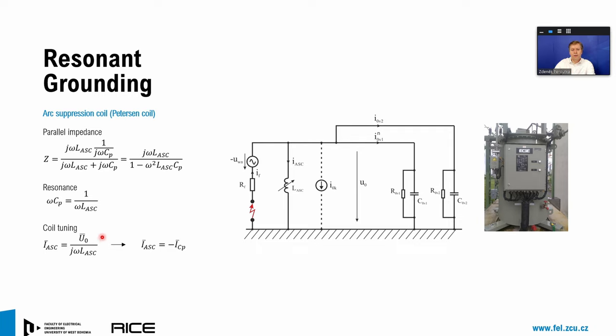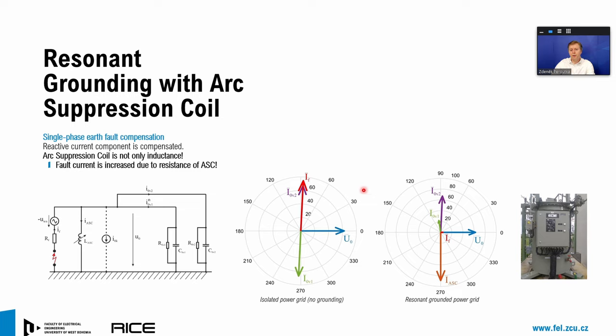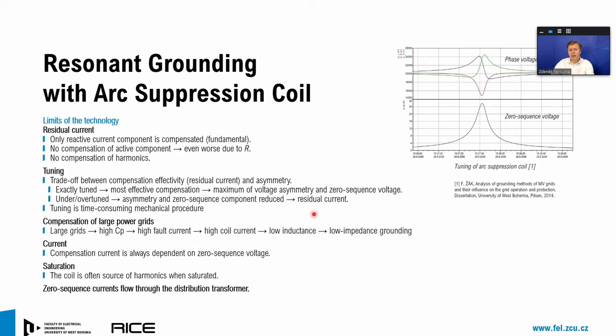The functionality of the resonant grounding or arc suppression coil can be explained in terms of the parallel resonance in between the arc suppression coil and the grid parasitic capacitance, or we can explain the functionality of the arc suppression coil in the form of a current source. We can imagine the arc suppression coil as the source of the inductive current, which is caused by zero sequence voltage on it, and this inductive current, which is produced by the arc suppression coil, acts against the fault capacitive current. So this is the state-of-the-art technology, having several limits.